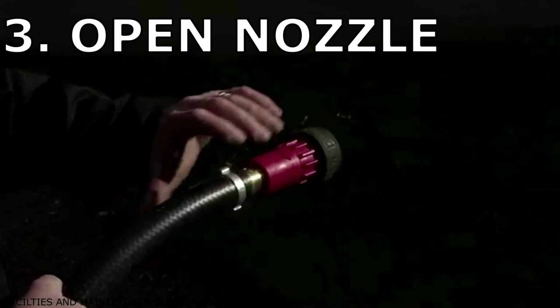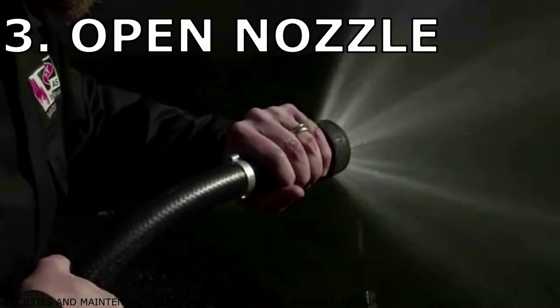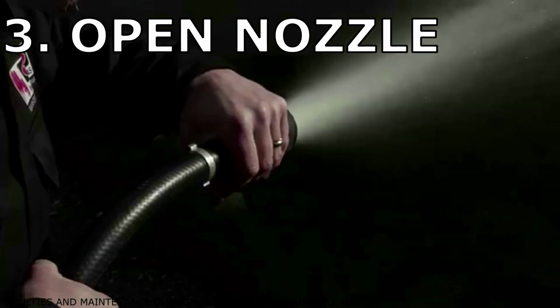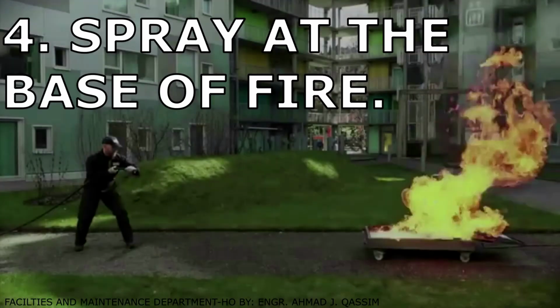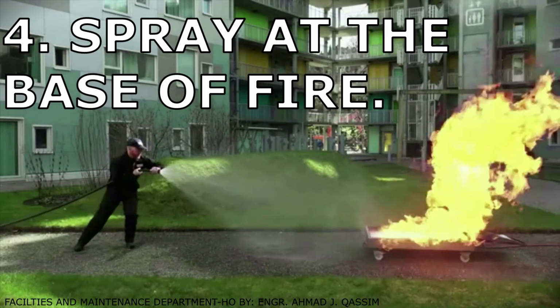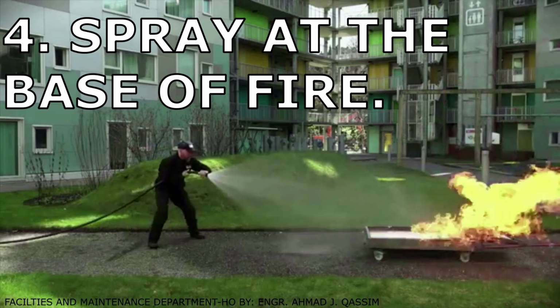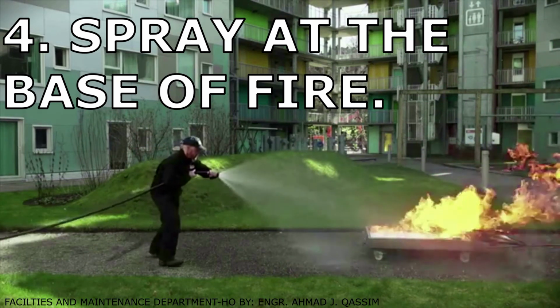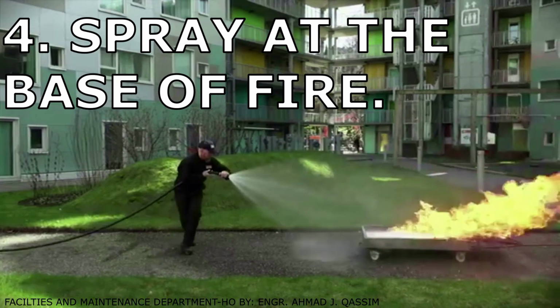Third, open the nozzle. Ensure the nozzle is fully open for unobstructed flow of extinguishing agent. Lastly, aim at the base of the fire. Direct the stream at the base of the fire. Only use sufficient agent to extinguish the fire.